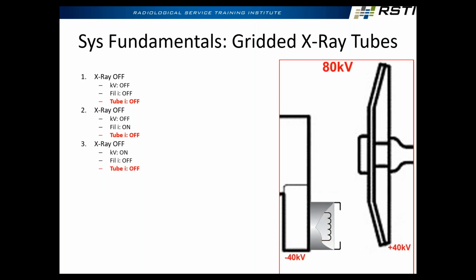This example has KV on, but filament current off. Still no radiation. I have a big voltage across there, but there's no current flowing, so no electrons to be sucked across there. No tube current, no radiation. Yes, sir. So, again, on the screen, what is it again? Nothing. Zero. The detector is sitting there. There'd be no trigger. It wouldn't be triggered for an exposure.